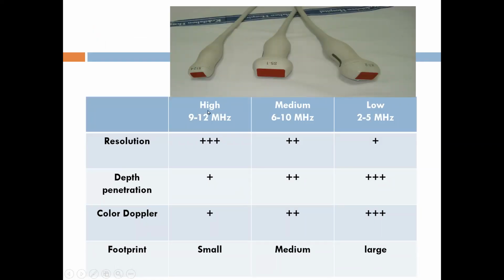Higher the frequency, higher the resolution. You can see two structures separately. So in neonates, where you have smaller valves, smaller structures, we will be able to differentiate and have a clear picture in small babies. So resolution is high in the high frequency probe. In the medium frequency, you have medium resolution, and in low frequency, the resolution is less.